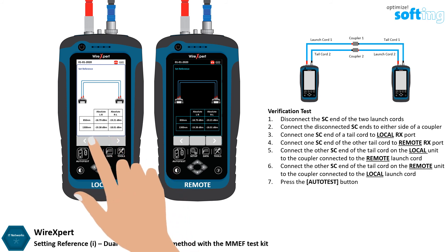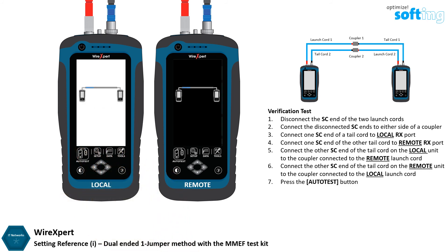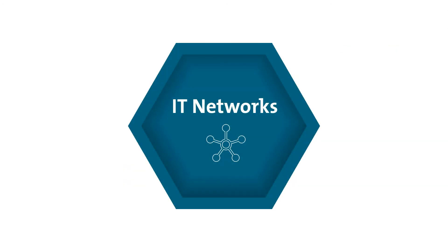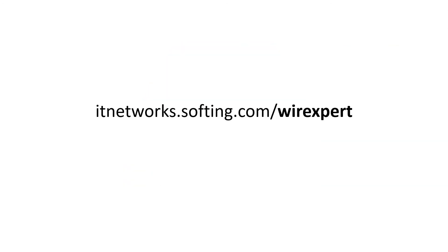Press the Auto Test button. Check that the result passes with a result not higher than 0.15 dB. The Dual Ended One Jumper reference method is now completed. Have a look at the other videos or visit our website to explore the other various features of WireXpert. Thanks for watching.